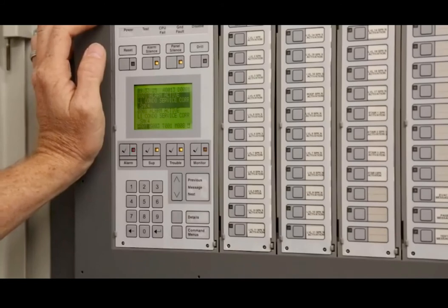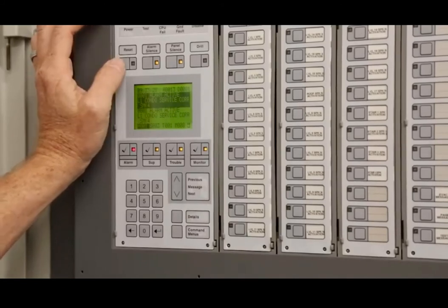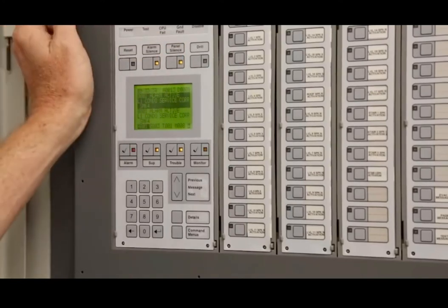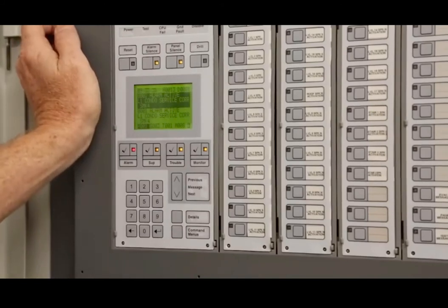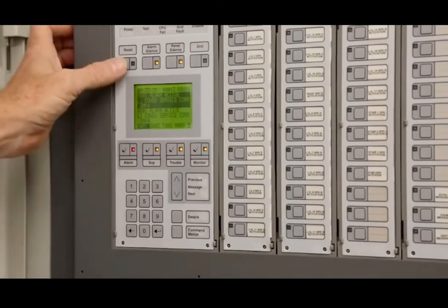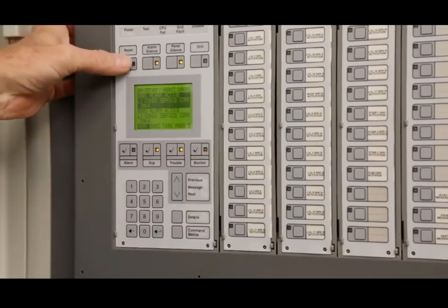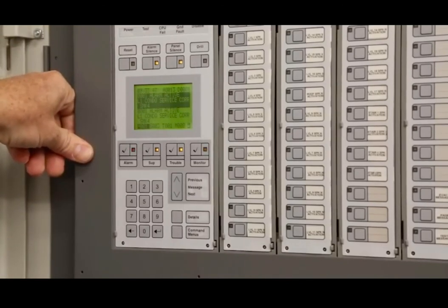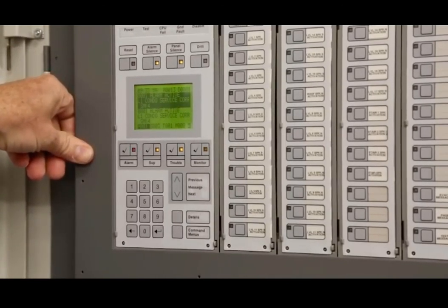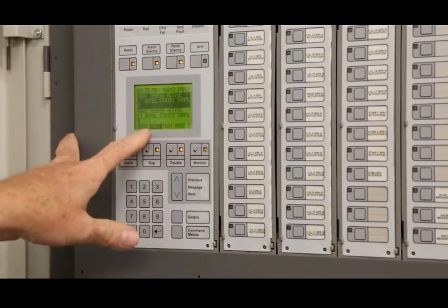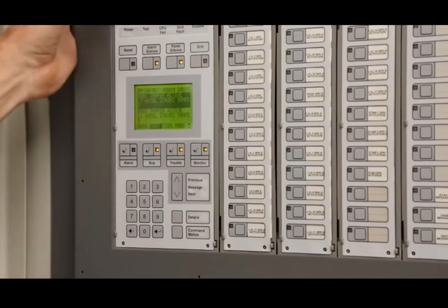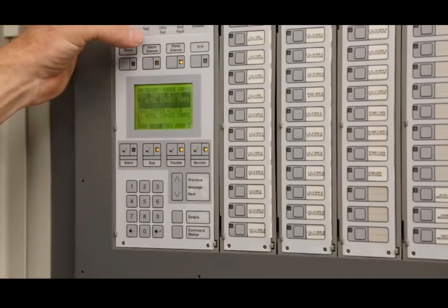You bring everybody in, after the fire department's here, you hit reset and the thing re-fires off. Now you're sending everything off. If the smoke detector is not able to reset, it will not let it be reset, okay? So, basically, we find everything is fine. We go in here, simply hit reset. Once you hit reset, it goes through its process. It takes about 10 seconds. You'll see the red light go off. Your alarms now went back to 0, which they were 1. Everything will go back to the way it presently was.